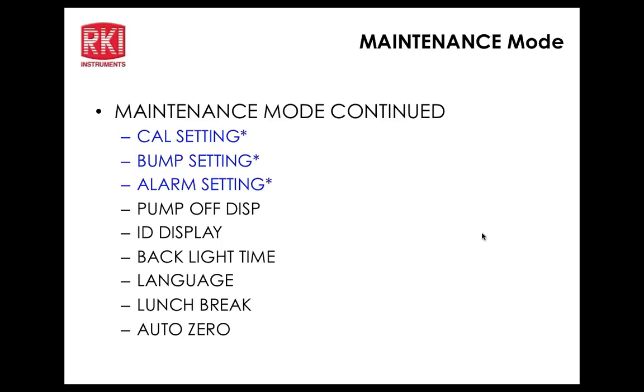All right, Tony, talk to me about the Port Authority. Thanks. Yeah, you're right. That came up with them. For some reason, they wanted to see extremely low levels of CO, and they objected to us having the 0 suppression. So yeah, you could go back to them with this instrument and be able to read right down to 1 ppm for CO. That's great. What it does, Daryl, the way the 0 follower operates is if the instrument goes negative for a period of time, and I think it's 1 minute, it knows that a negative reading is not possible, so it'll bump the reading back up to 0. I got you.